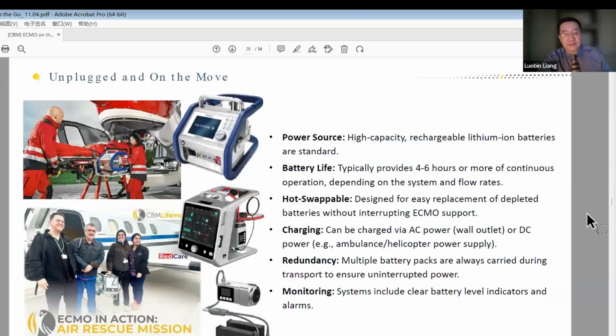Also, we need the system to have power, right? So we need an unplugged system on the move. So we need a high capacity rechargeable lithium-ion battery. That's a standard. So usually this type of battery can provide 4 to 6 hours with a continuous operation, depending on the system and the flow. And also when the power of the battery depletes, when we want to change the battery, we want a hot swappable. So when we're changing the battery, it does not interrupt the ECMO support.